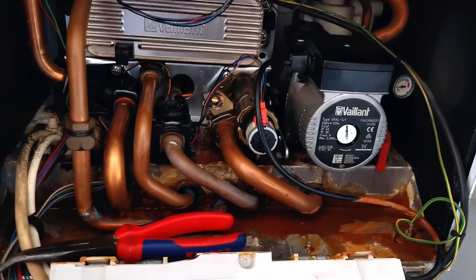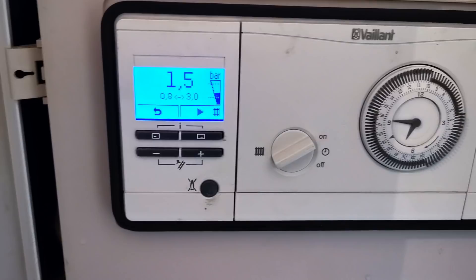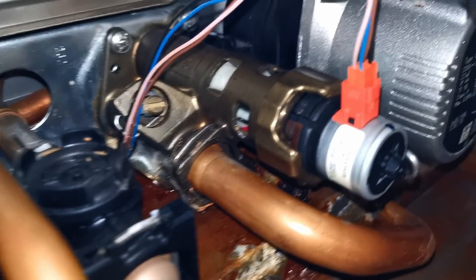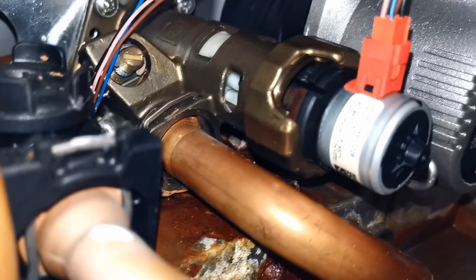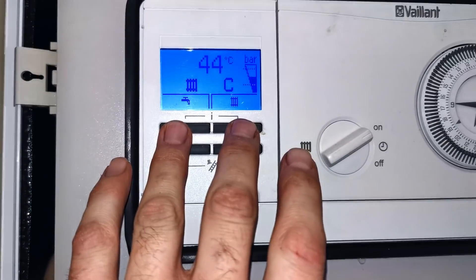Plugging the electrics back in, drying up in here a little bit, and then I'm going to put water back in it. One and a half bar in there. I checked the valve — it doesn't leak, the spindle moves in and out beautifully. Job done — or so I thought.